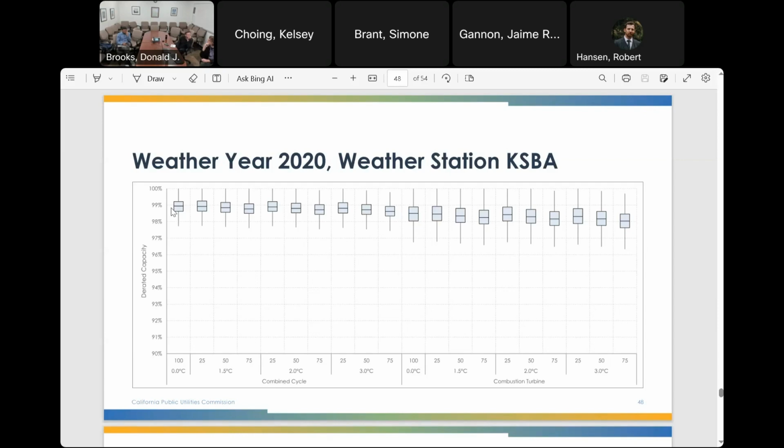Got it. So have you thought about whether or not this will impact the forced outage rate that you use in the LLE study itself? The forced outage rate comes from GADS data, which looks at equipment failure, not ambient temperature. It's possible that there is equipment failure due to hot temperatures, but I would imagine that most of the equipment failure is due to overuse, just its use patterns.